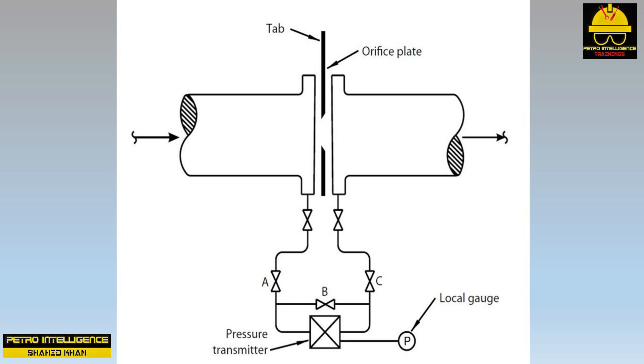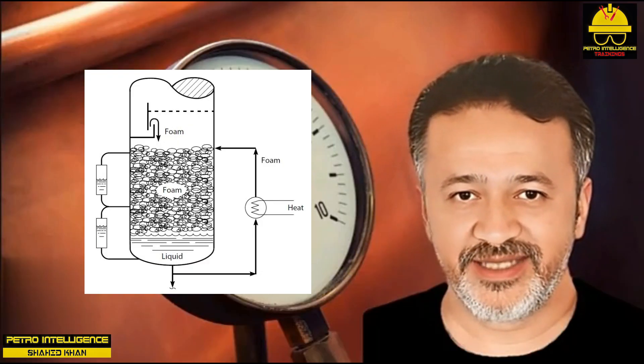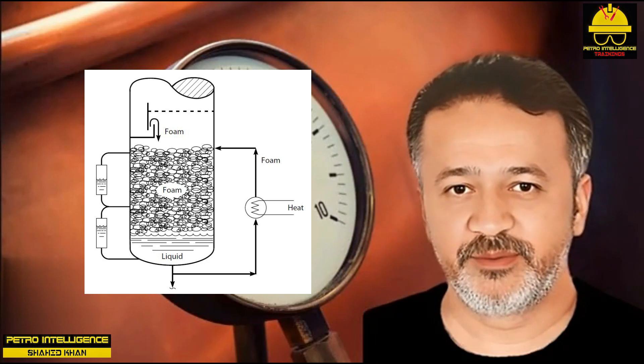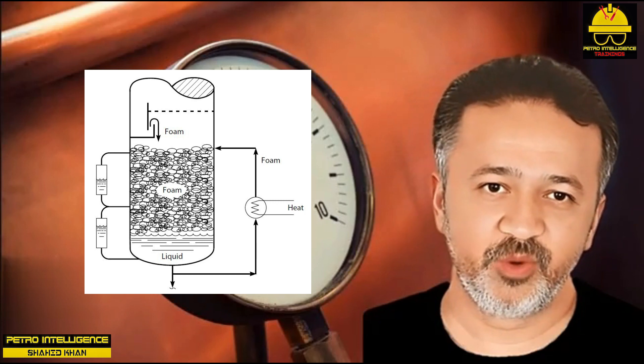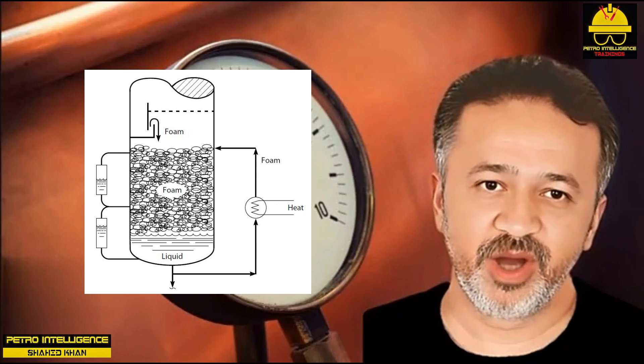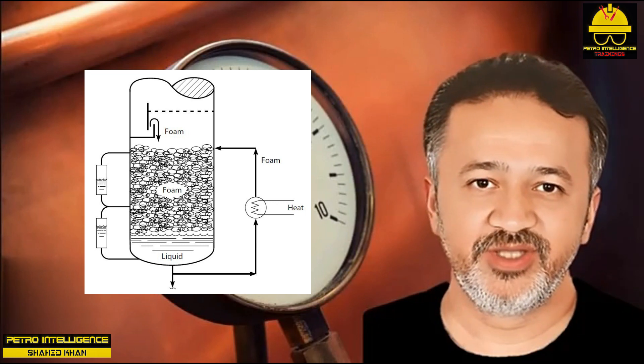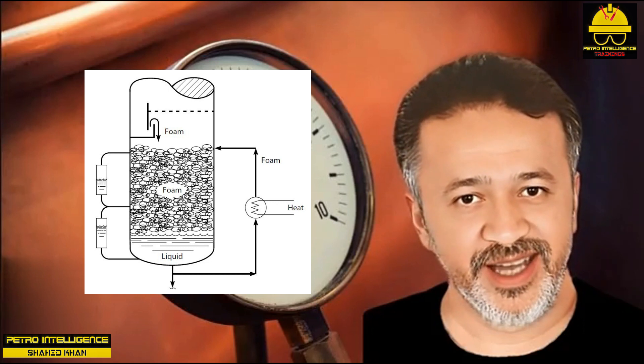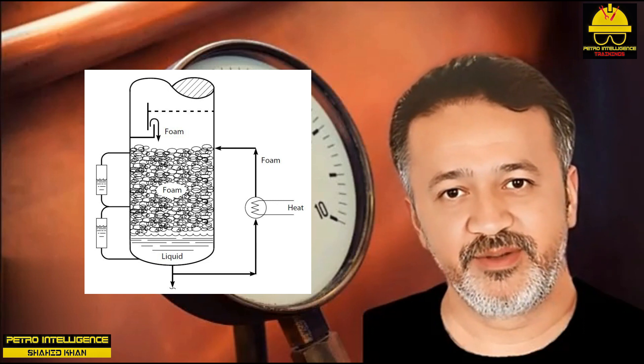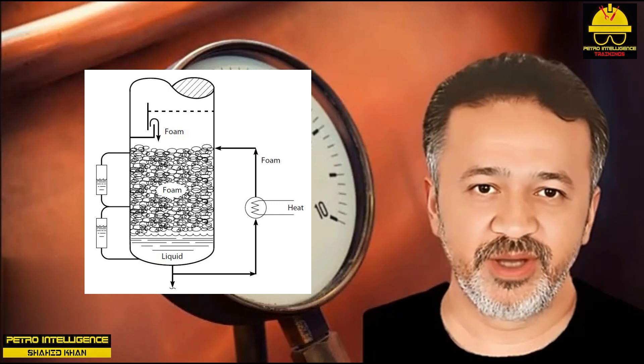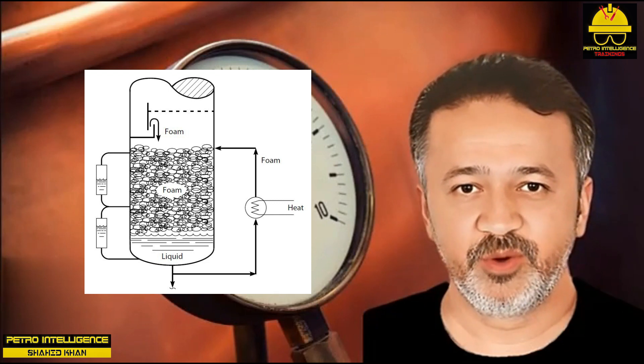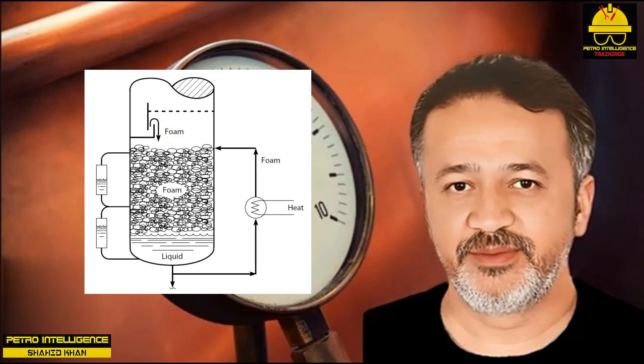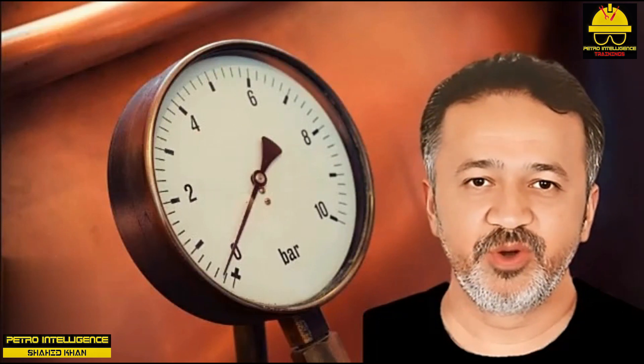The governing equation is: ΔP = K × df × V² ÷ 62.3 × B², where ΔP is the measured pressure drop through the orifice plate in inches of water (multiply measured psi by 27.7 to obtain inches of water), V is the velocity of the fluid through the orifice plate in feet per second, df is the density of the fluid in pounds per cubic foot, and K is an orifice coefficient — typically 0.6 to 0.8, found in your Cameron or Crane handbook.